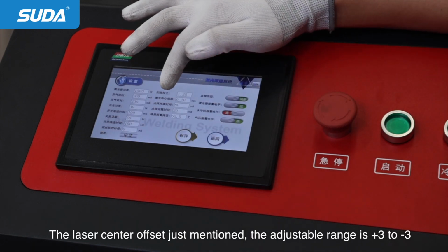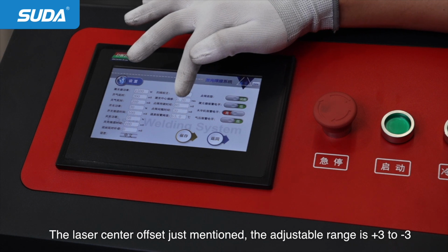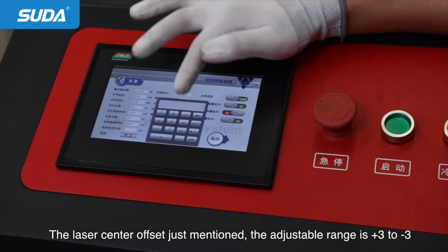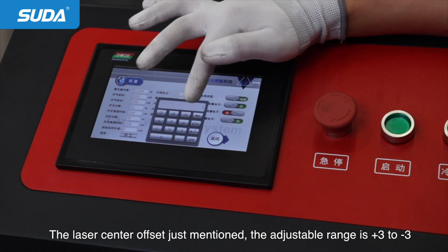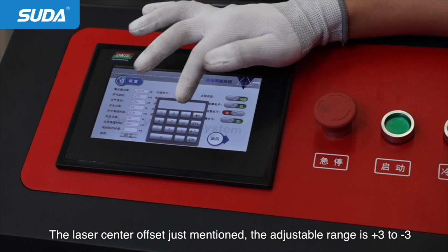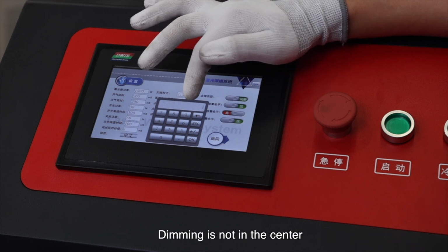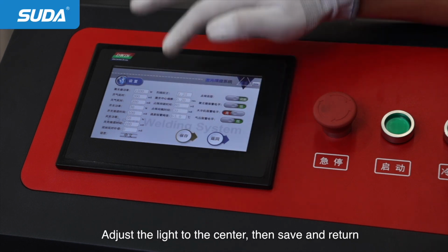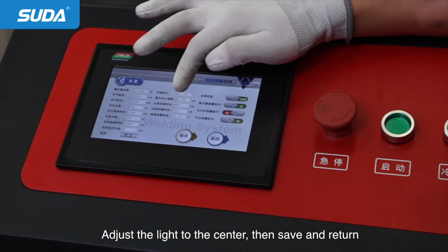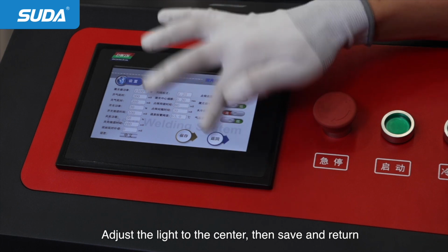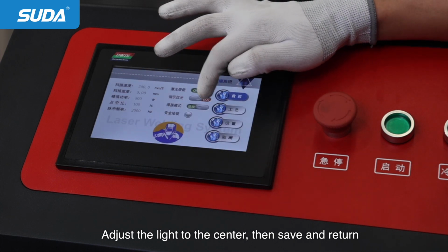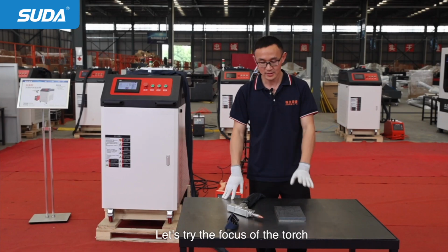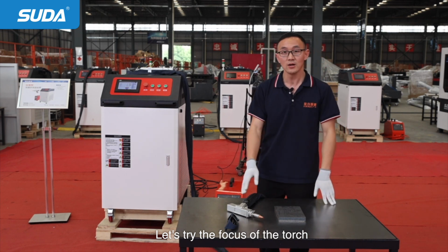For the laser center offset just mentioned, the adjustable range is +3 to -3. Check whether the light is in the center. Adjust the light to the center, then save and return. Let's try the focus of the torch.